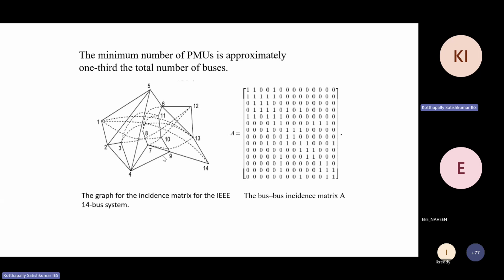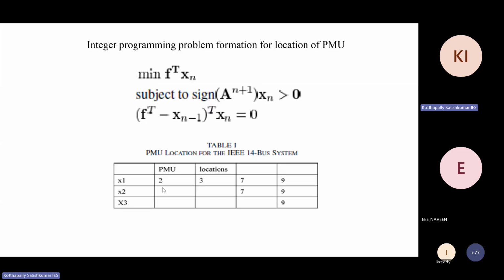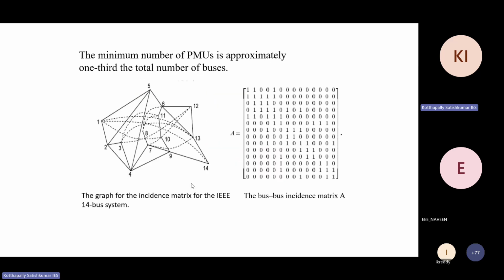So accordingly, if you choose PMU locations in a proper way to measure all these 14 nodes, you do not require 14 PMUs, but just 4 PMUs to know the voltages at each and every bus. If you know the complex bus voltage at each and every bus, then we say the system is observable. In order to control the system, it should be observable. If you are able to observe the system, then only can you easily control it: observability and controllability.